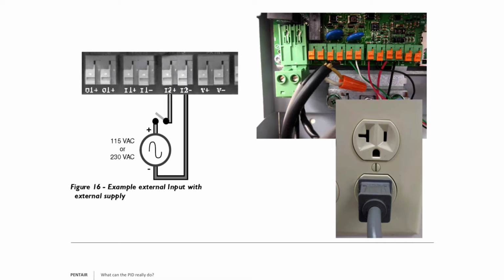So for input 2, we would go into our main menu, if need be, enter our password again, scroll down to input, output, I/O, enter, scroll down to input 2, enter, to highlight the box. It'll probably say unused, of course, because we're not using it. And then we're going to scroll till it says run. Hit enter to save it, and then the status button to pull out again. So we're back to the main menu.